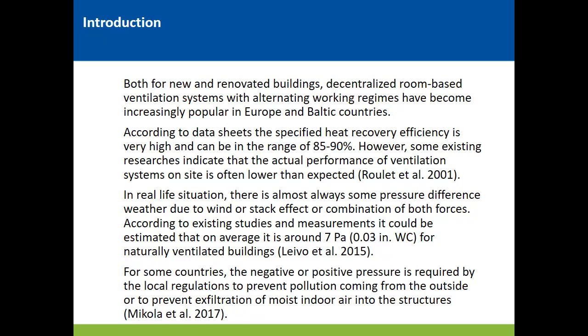They usually state this efficiency just at 0 pascal pressure difference between indoors and outdoors, but in real situations there is always some kind of pressure difference, either due to stack effect, or due to wind, or due to local regulations that require some negative or positive pressure in the buildings. So our task was to determine how this pressure difference actually influences the actual heat recovery efficiency.